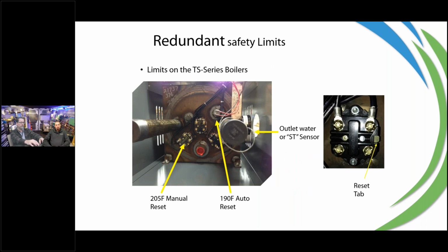Redundant safeties - every time we talk about electric, you'll have different limits built in on top of the boiler: a 190-degree auto reset and a 205 manual reset. You can see that tab on the right of the screen. So if it did trip at that 205 mark, you figure out what's going on in the system causing that temperature rise, and then you can just manually reset it from there.